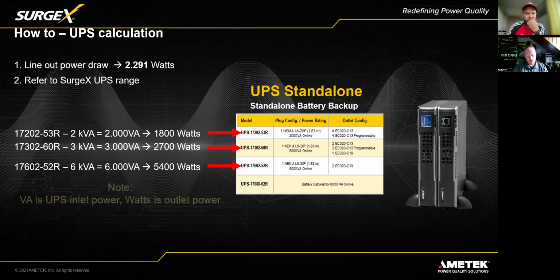That's also very important: what's always mixed up is that VA is the inlet power, but watts is the outlet power. Mostly we get questions where somebody calculated 2000 watts as their use case and then asks for a 2000 VA UPS. But that's not enough, because there's always an efficiency factor with the UPS, so it doesn't supply 100% of the energy you put in.